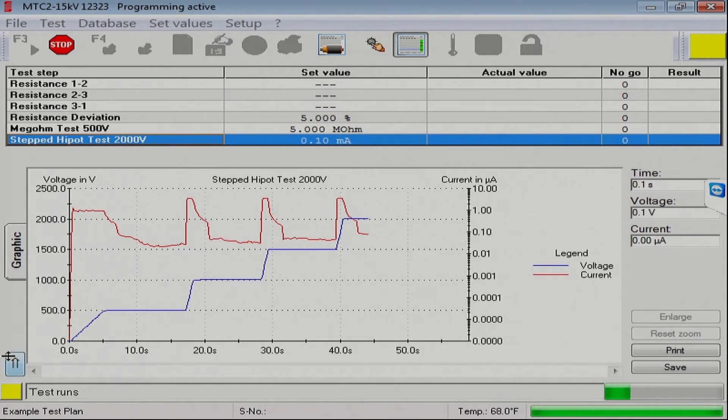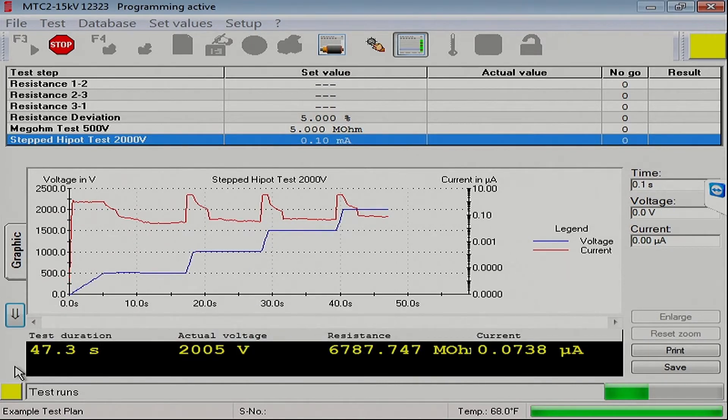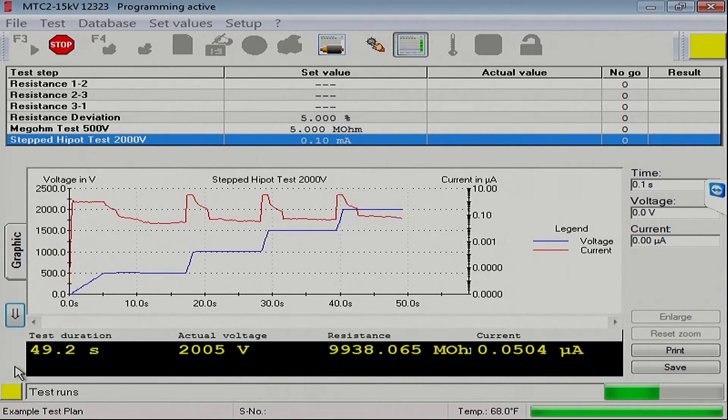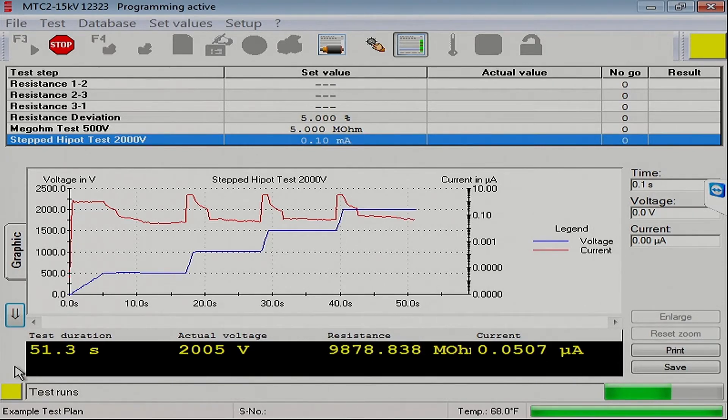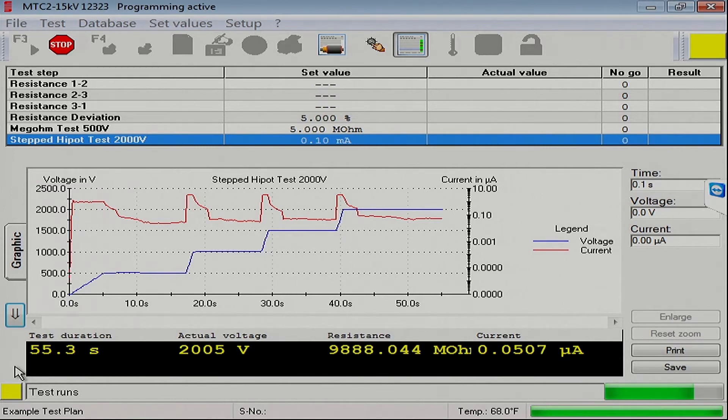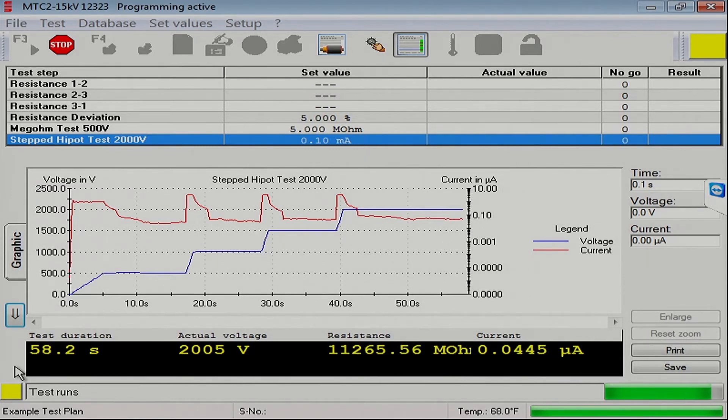Again, this double arrow key thing here in the left-hand corner, if we press that, we actually get values that it's reading. The stator that we're testing right now is a very small one. And as you can see, the leakage currents are very small, very low.